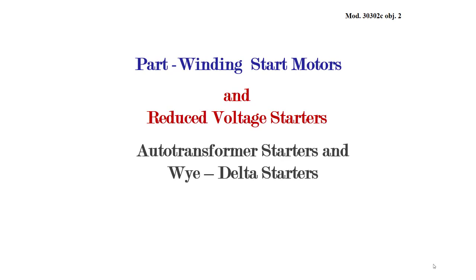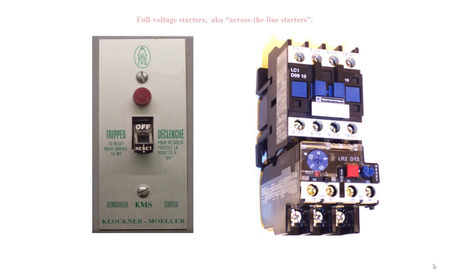Right, we're going to have a look at the three-phase motors and starter module, focusing on objective 2. So this is part winding start motors and reduced voltage starters. Part of the two reduced voltage starters are going to be the auto transformer starters and the Y delta. So those are the true reduced voltage starters. There's also some code rules that you could reference for this module as well. Please have a look at those.